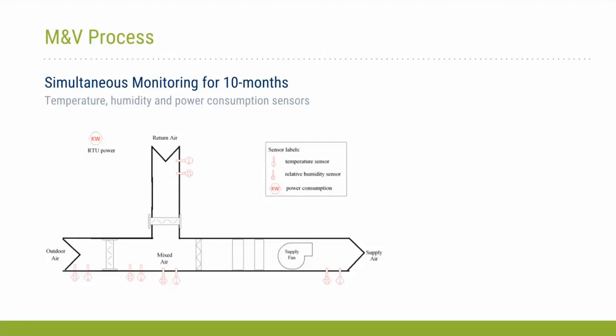And then for the high performance unit, because the unit modulates the supply fan, we basically did a one-time measurement of the fan flow as a function of fan speed, because we cannot measure fan flow or airflow continuously in the field. But we can measure the speed of the fan. So if we can correlate the speed with the flow, then we know what the flow is at any given speed. So we did that one time. And then this allowed us to estimate the cooling load on the coil. And we also measured the total energy consumed by the unit, which allowed us to estimate the installed energy efficiency ratio for both units. Next slide, please.